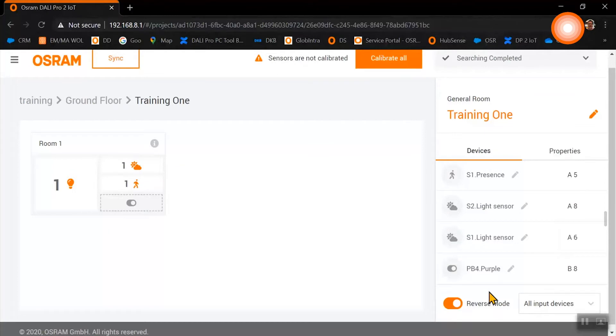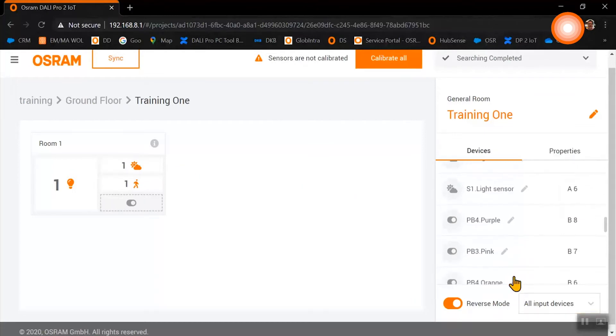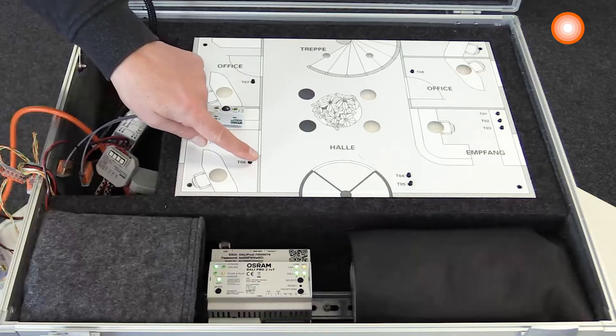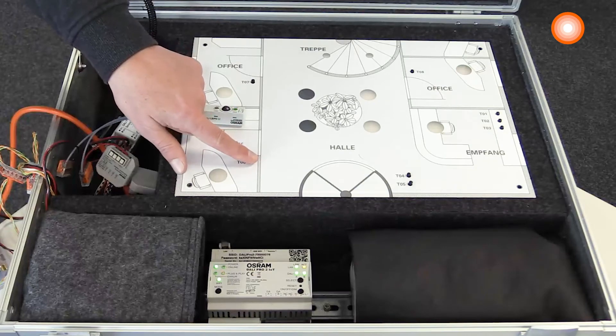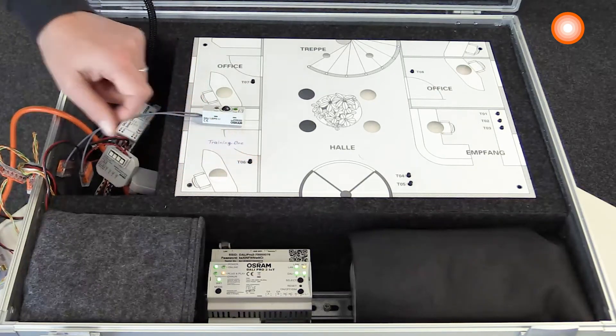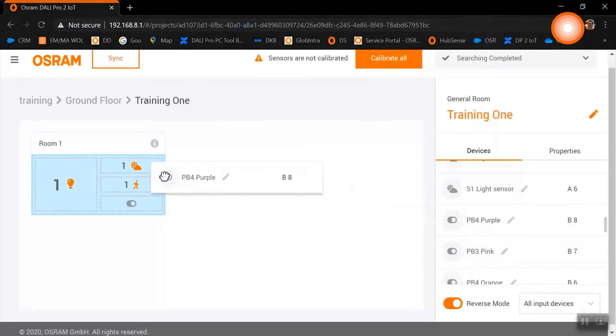As we want to have additionally a push button in our room, we need to identify this one as well. As the reverse mode is still activated, we are just clicking the push button and the push button identifies itself. Via drag and drop, we take the push button into our room.